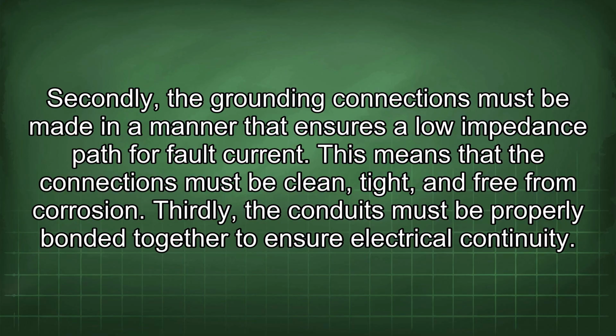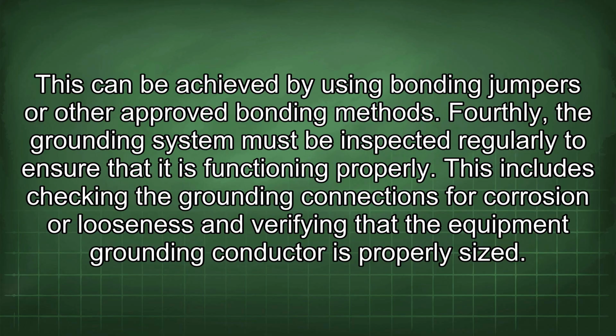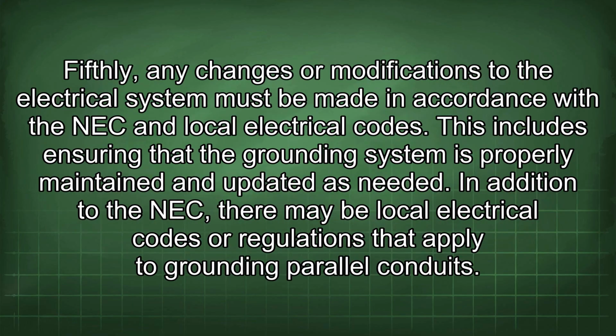Thirdly, the conduits must be properly bonded together to ensure electrical continuity. This can be achieved by using bonding jumpers or other approved bonding methods. Fourthly, the grounding system must be inspected regularly to ensure that it is functioning properly. This includes checking the grounding connections for corrosion or looseness and verifying that the equipment grounding conductor is properly sized. Fifthly, any changes or modifications to the electrical system must be made in accordance with the NEC and local electrical codes. This includes ensuring that the grounding system is properly maintained and updated as needed.